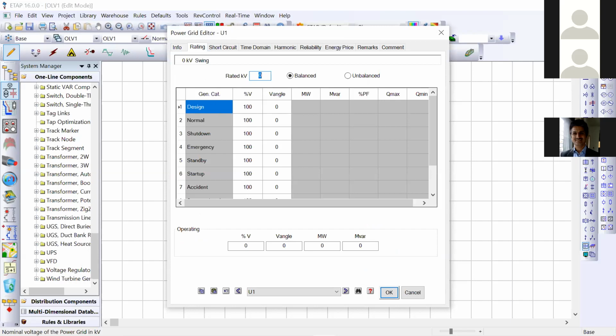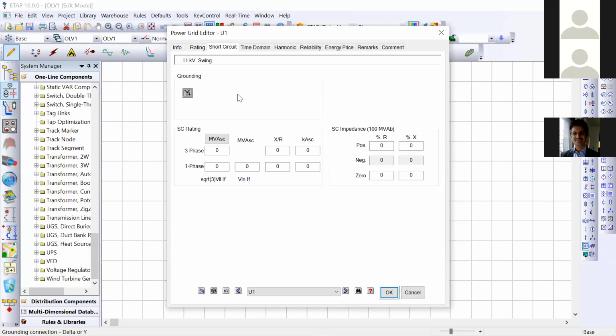Rated. Generally, for common installations, a small industry, a small commercial, or a small or large residential, 11 kV connections are generally available in India, in most of the states and most of the utility boards. It is a balanced source. A short circuit level of the source we have to give. So 11 kV at 500 MVA I'm giving. This 500 MVA is normally available. These are the figures we generally use because this is normally available with most of the distribution companies. That's the reason we have taken this source short circuit level.